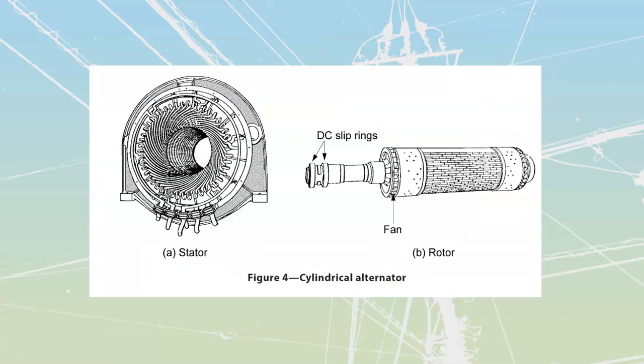If I want relatively high-speed operation, I'm going to have to go to a cylindrical rotor, and it's going to be a much longer and skinnier type of thing. The reason we go longer and skinnier is because we have less centrifugal forces acting upon my individual windings inside of it.